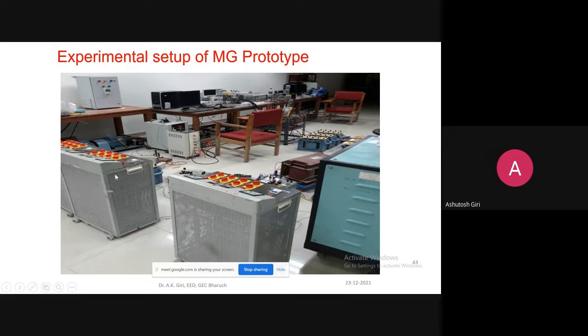These are the loads, and these are lamp loads, basically treated as resistive load. So that was the power circuit. This is the converter—a 4-leg converter. You can see the terminals: red, blue, green, and three points are taken here. We made the PCC, point of common coupling, at the top of this rack, from where the generator, supply terminals, load terminals, and compensator terminals are connected.